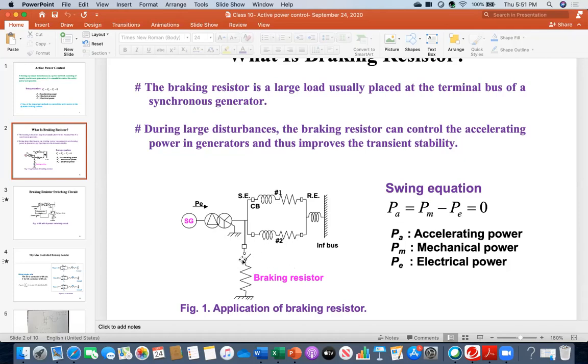So this means that this control should be adaptive, and there should be a good mechanism. It is not just that it collects a signal, there is a fault, and it closes and opens. There should be something in the switching. You can keep the resistance fixed, for example 1 ohm or 10 ohm, but there should be a power electronics based control mechanism that can control the power consumption. The resistance value can be fixed, but you have to control the flow of current. For example, during a 3LG fault, if 100 ampere flows, then during a 1LG fault, let only 5 ampere flow.